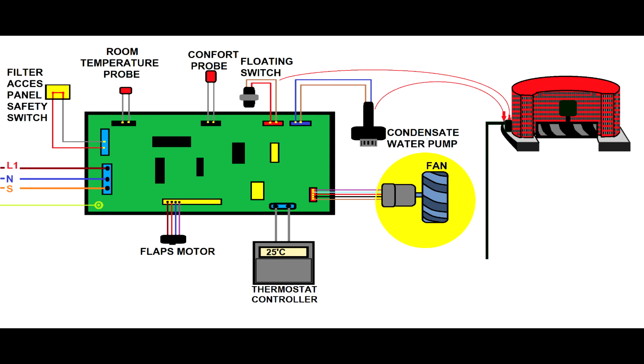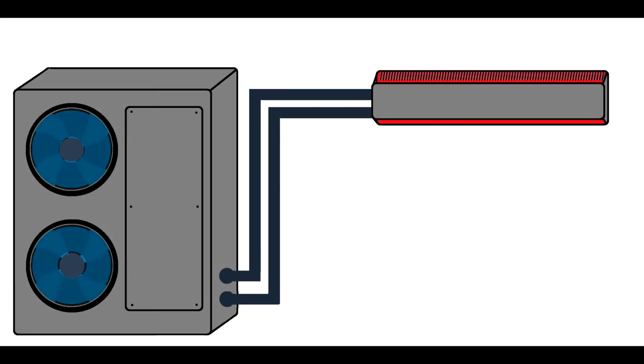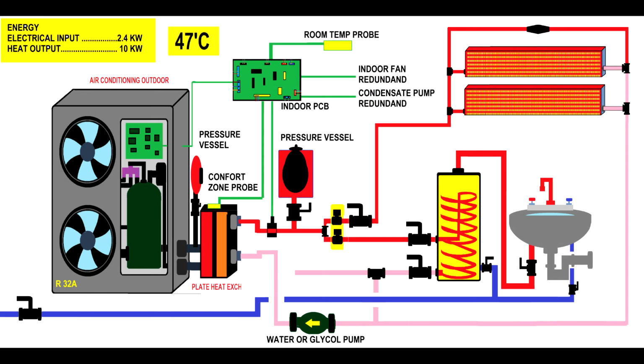In the winter you don't use that floating switch, you don't have water in the drip tray, so your unit will work because the heat exchanger is hot. You don't have any condensed water on the heat exchanger, so the pump will not work. The same with the split system, but the split system never uses pumps unless you want to push the liquid upwards. Normally it goes naturally down, but I installed a lot of pumps, because I have to send the condensate water far away, horizontally.